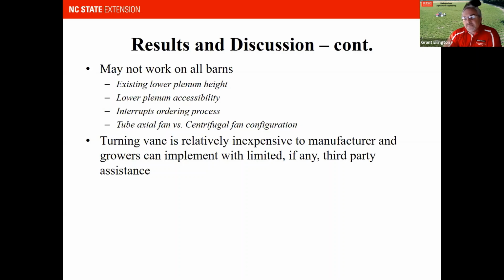This may not work on all barns. The range of existing lower plenum heights is 14 to 22 inches, and lower plenum accessibility varies; a lot of barns don't have a back access door, so there's not an easy way to get underneath the fan without pulling up the floor, which takes a lot more time to actually install a turning vane. So the barns we're using were picked strategically because we've got easy access to the back of the barn.